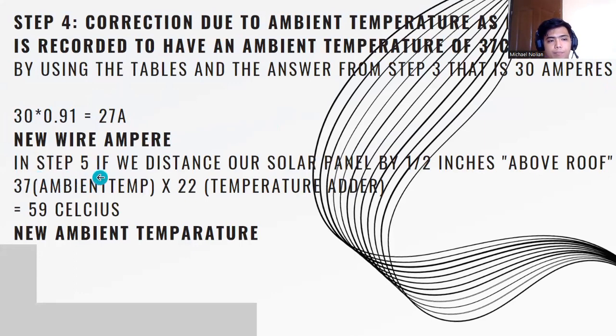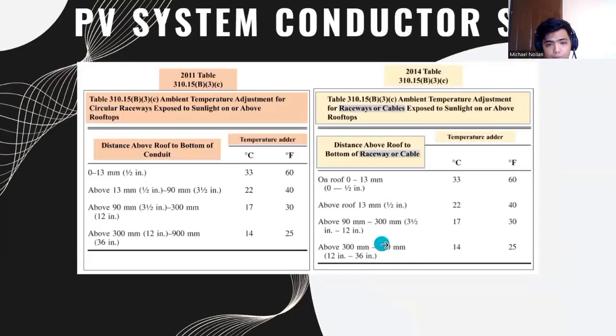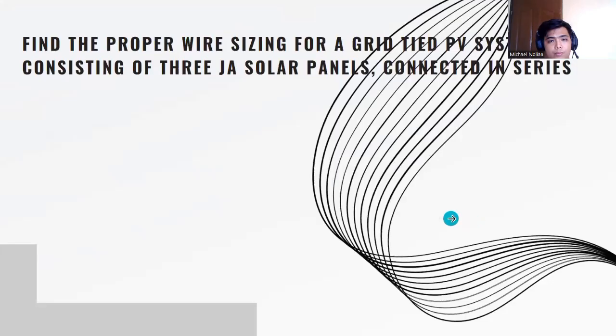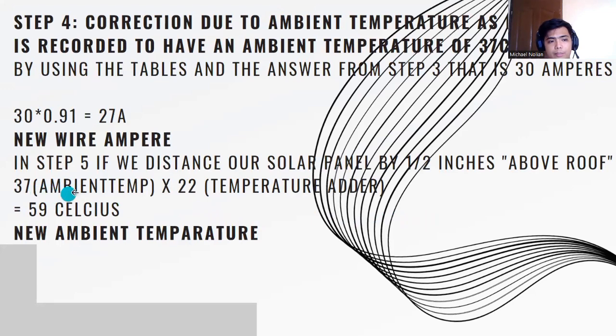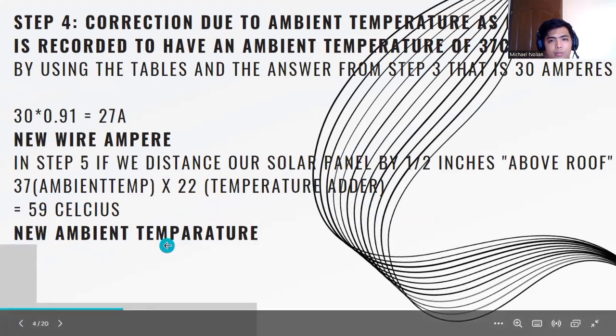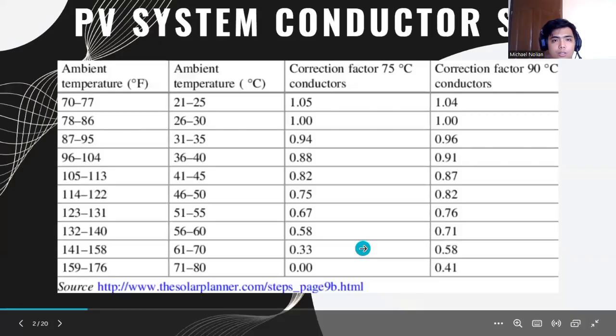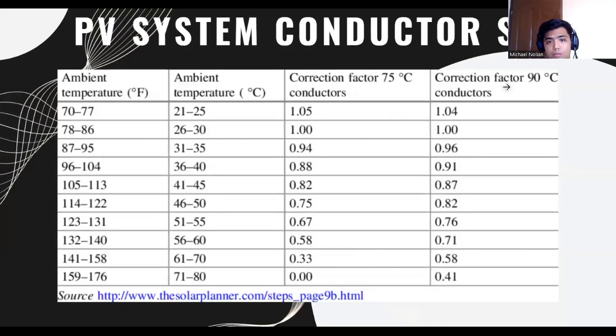In step 5, if we distance our solar panel 1/2 inch above the roof, note that, this will be the calculation: 37 ambient temperature plus 22, the temperature adder, for above roof. As I said earlier, above roof. So 59 degrees Celsius is our new ambient temperature experienced by the conductors.